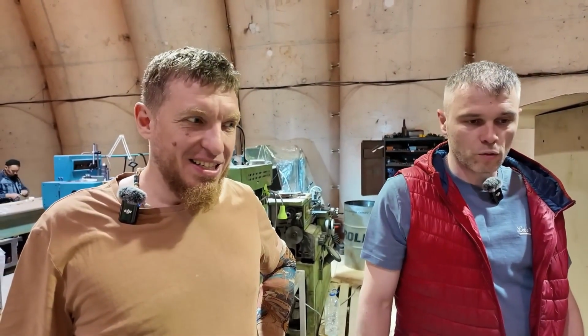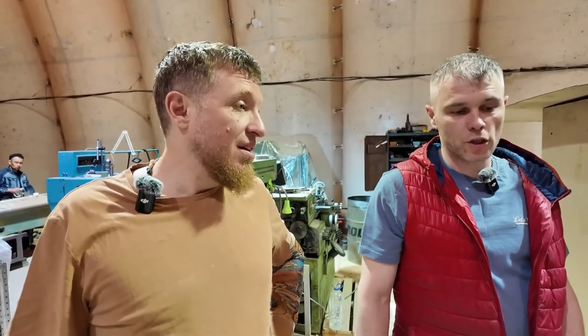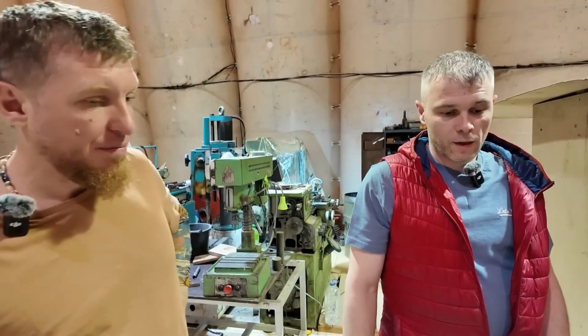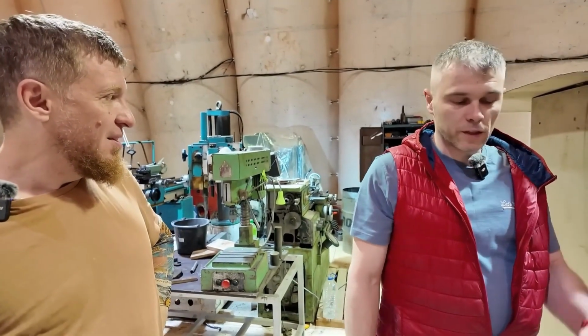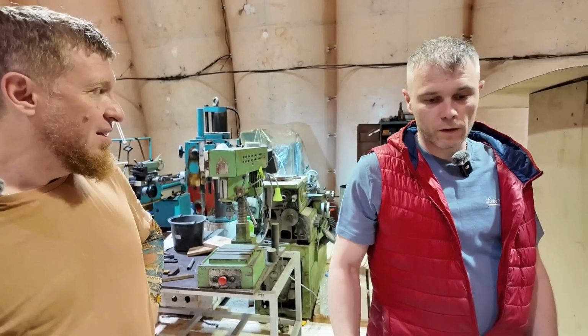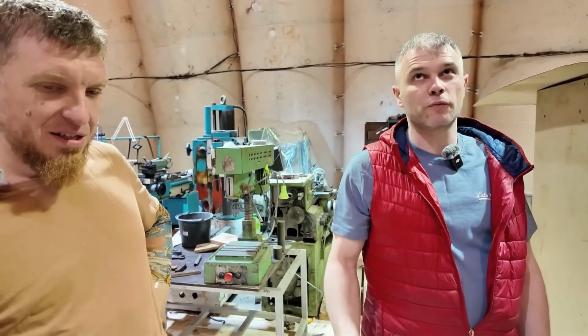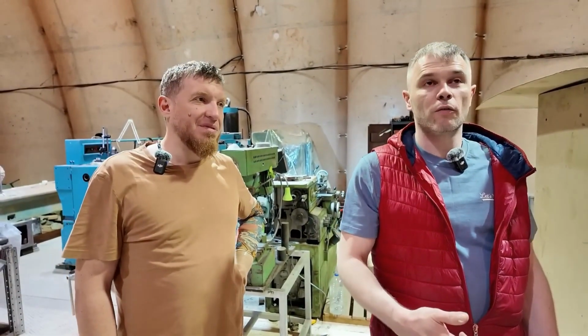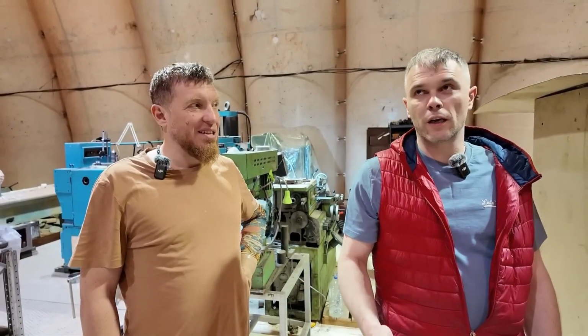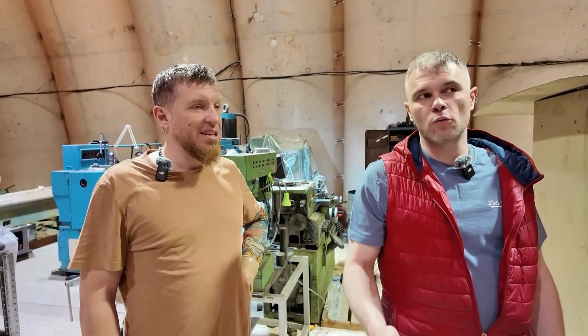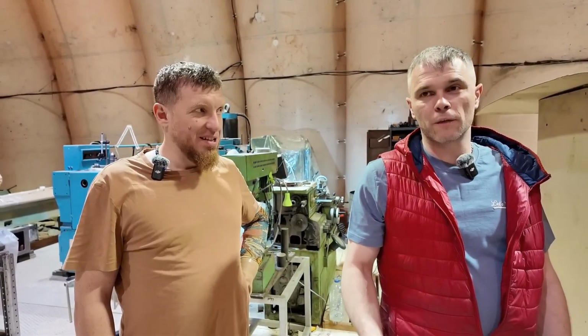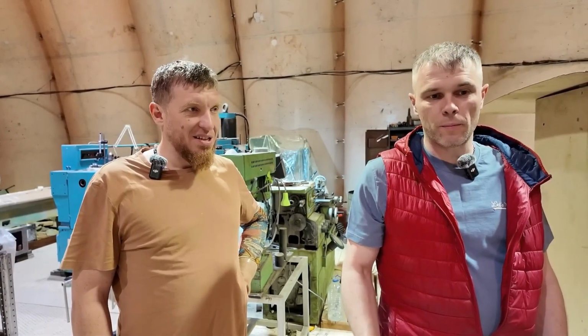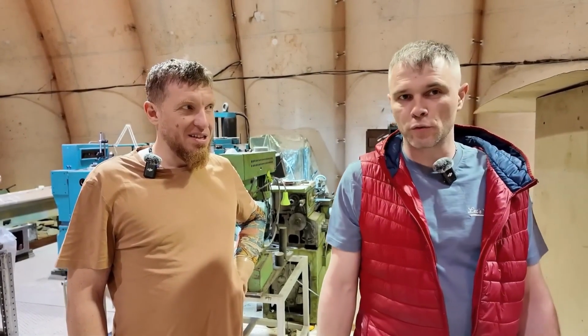We tried it, you said we need an encoder. An encoder, yes. Right now we're looking for a high-quality encoder that provides at least 21 bits, and preferably 24, with a large diameter. There are some important nuances. We tested our controllers, no issues at all, using an automotive resolver. They provide an accuracy of about 40 arc seconds. That's about 3 to 4 times worse than what Soviet machining centers used to deliver.